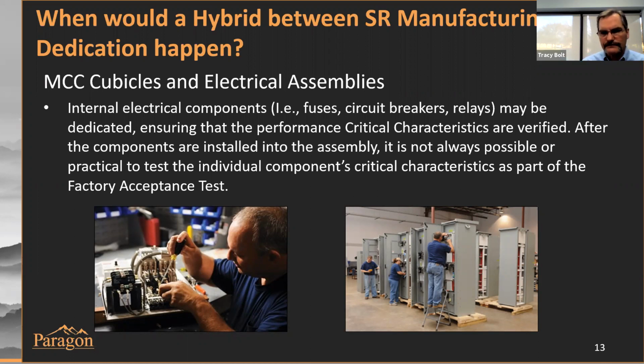Take a circuit breaker, for instance—if you need to verify its performance characteristics like a trip curve, there's a special way you need to test the breakers to ensure it's done properly. You need the right length of wire when connected to the high current test set, and if it's installed into the bucket, it's really hard to get consistent results given the set standard for how you need to test those items. But testing a thermal overload relay on a starter, and other items within the bucket, it's a lot easier and more efficient to test and dedicate them prior to assembly than trying to test those characteristics after they're installed.